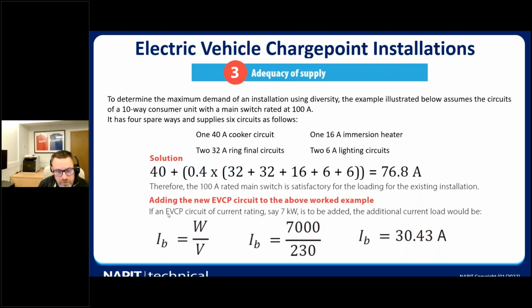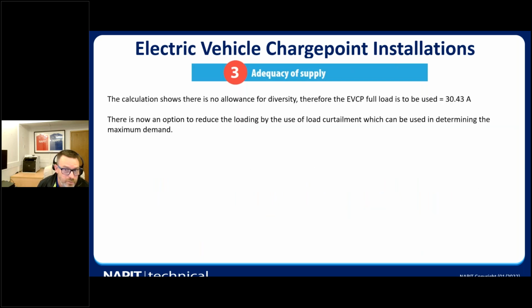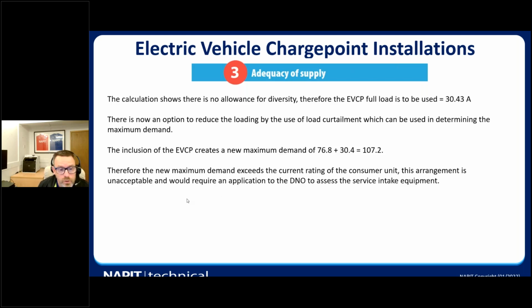So if we're going to install a new EV charge point, say a 7 kilowatt point, we're looking at adding an additional 30.5 amps onto the installation. That would take the installation over 100 amps, so we're looking at possibly using load curtailment. So you're looking at a load management system to cover this and make sure the EV charge point is only in use when the installation allows it. That would allow the maximum demand to be covered if you were using load management.